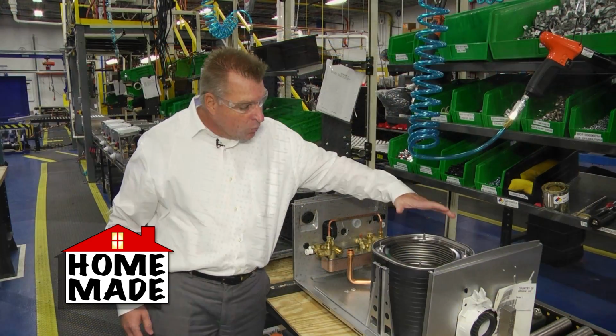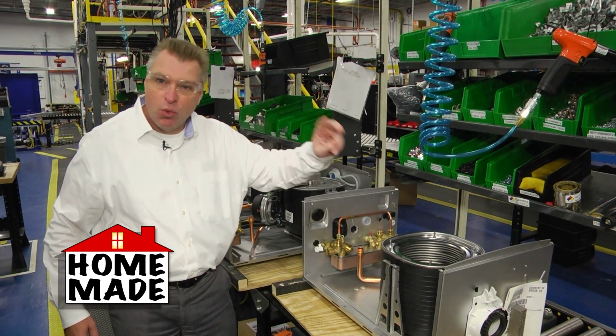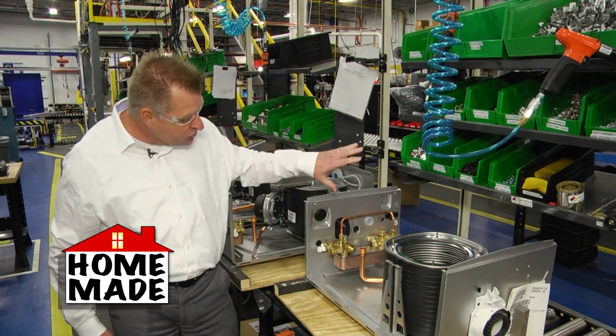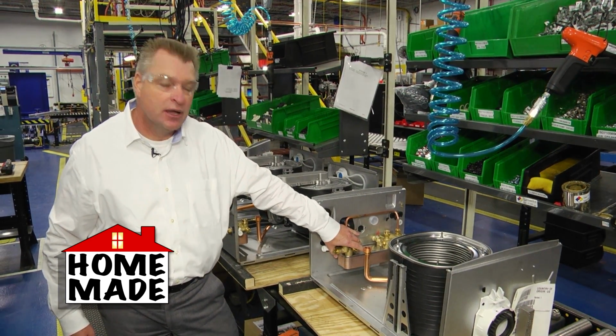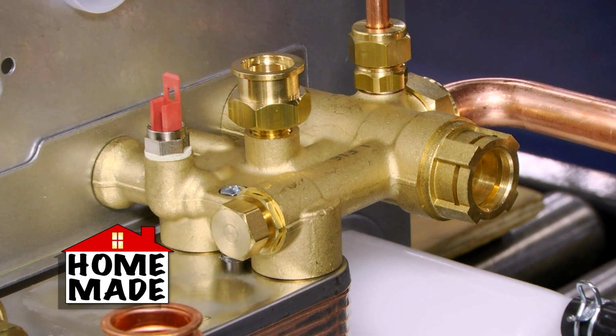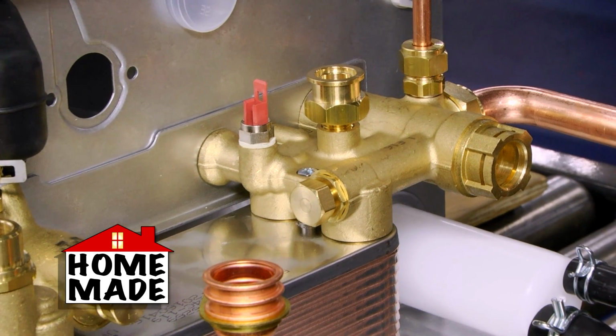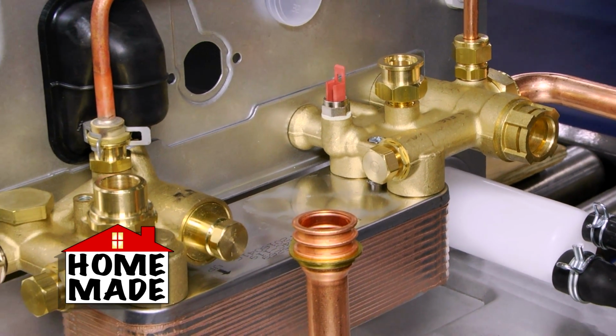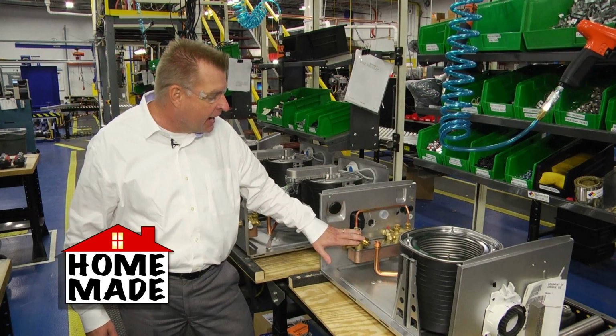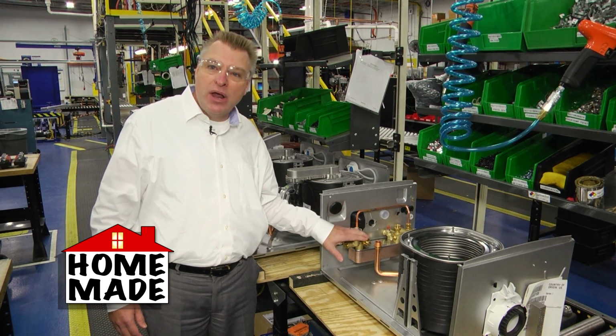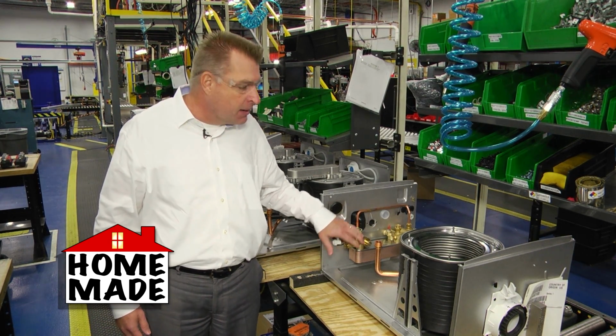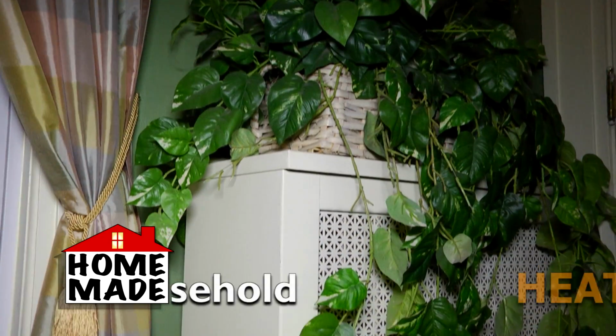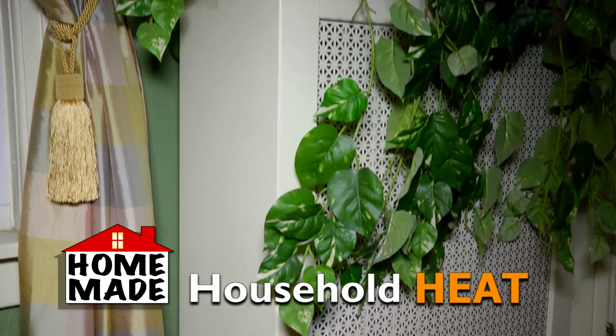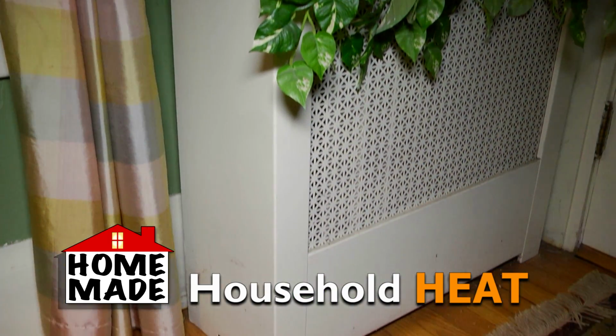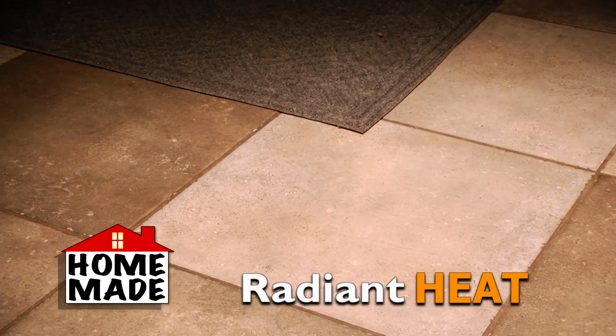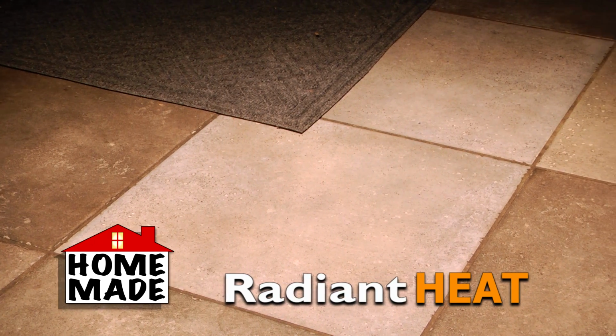The water, once it's heated up, is now pumped one of two ways. It's either pumped to what's called the combination unit, which is basically another heat exchanger that provides a heat source for your domestic hot water, your showers, your kitchen sink, things like that. Secondly, if you don't have that need for water at that moment in time, the unit will provide the hot water to your heating for your house. So your baseboards, it could be your radiant floor, those types of things. So the unit is really multi-purpose in that nature.